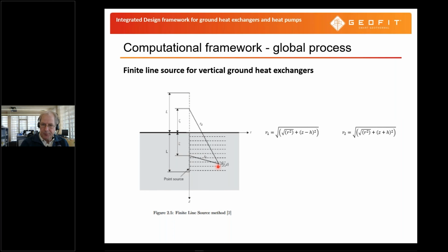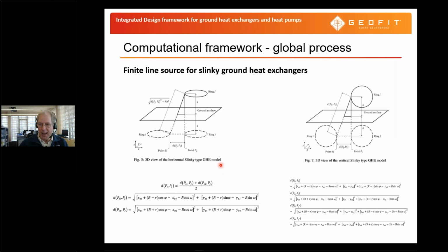The same type of approach can be used for a ring type heat exchanger, where here we have a ring and then here we have another ring, so a slinky type or ring type, and then the mirror sources are again on top of the surface defined and cancel out slightly the closer you are to the surface. And we can do that for flat rings, but we can also do that for horizontally, vertically oriented rings. I'm not going to explain all the equations because that goes much too deep into the theory.